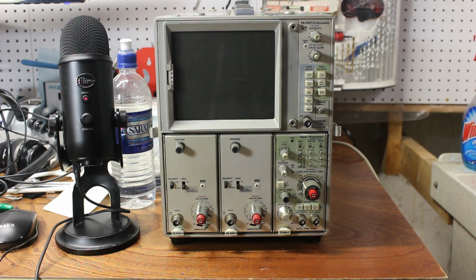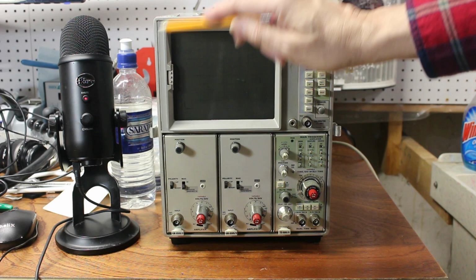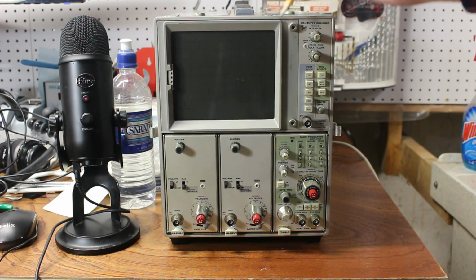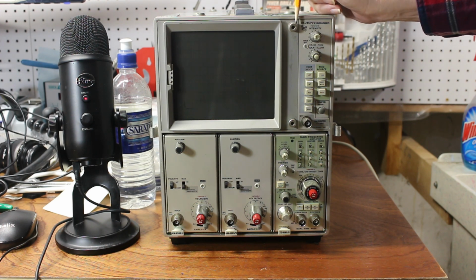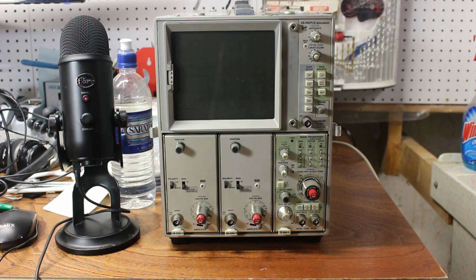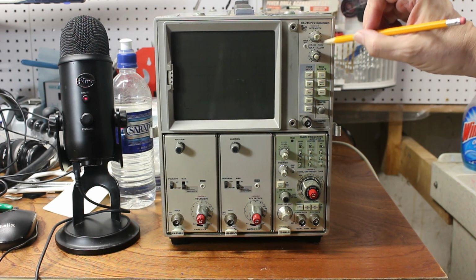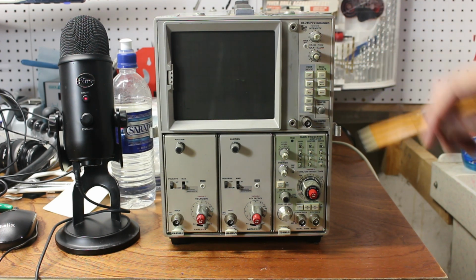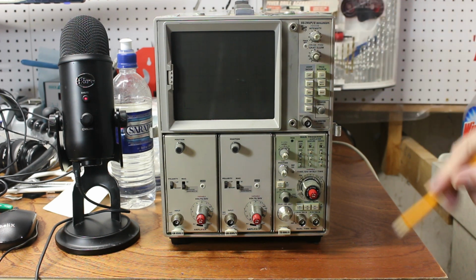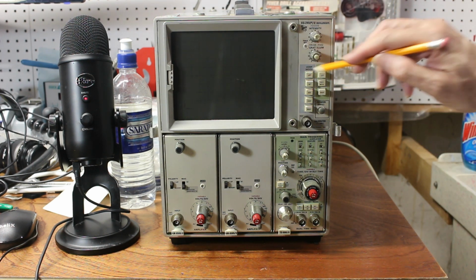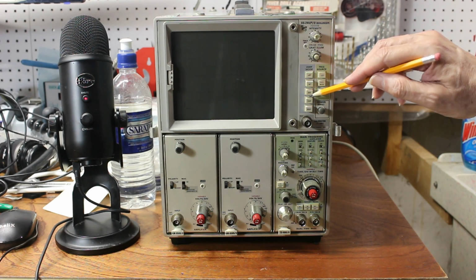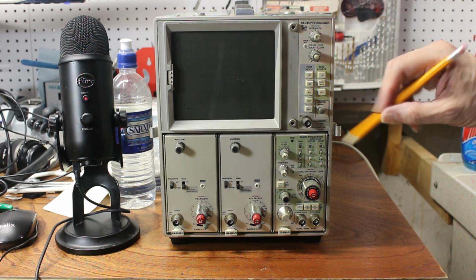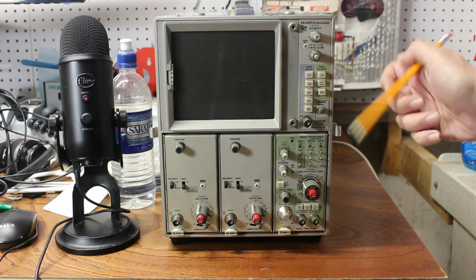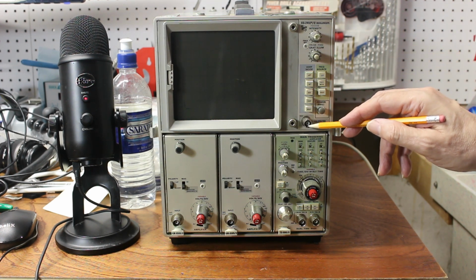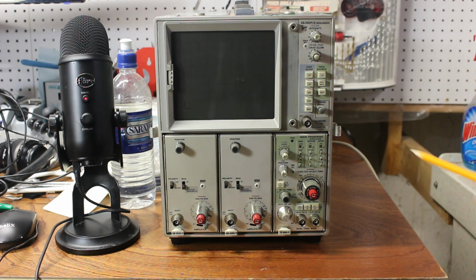It's designed like a lot of Tek scopes of the period. It's got a mainframe unit on the top that has a CRT display, including a clever little fixture for a Polaroid camera, and the controls for beam intensity and focus, graticule illumination, a button for a beam finder, and a couple of display modes: left channel, alternate, add the channels, chop, right channel, and a trigger source. It's got the power switch, and it's got a calibrator output. Then across the bottom, there are bays for plugins.